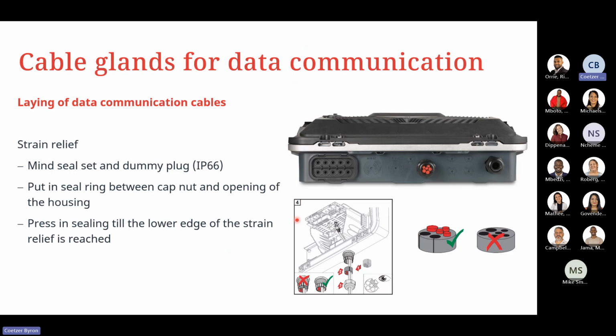Next, and importantly, is the cable gland for your data communications. Typically what we've noticed is clients will remove entirely all these red plastic stoppers from the gland and then simply throw them away. This will affect the IP rating of the unit itself. So what we recommend is to always remove only the plugs that you need to remove. If we have two cables coming in, we simply remove two of the plastic stoppers, have our cables coming through, reinstall this rubber with the plastic stoppers, and then refasten the gland back into place.